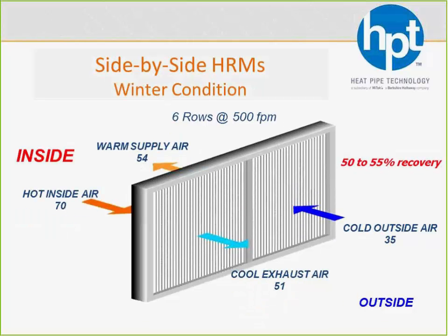And then conversely, when it's cold outside, now we're going to take the heat from the exhaust air and put it in the outside air stream to preheat that air so the boiler or whatever's being used for heating doesn't have to work as hard. And it's still going to be the same effectiveness, about 55%.